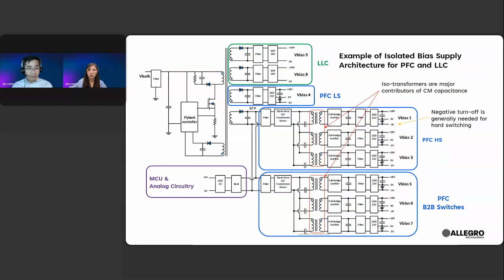An example for the PFC high side negative supply design: we get 12 volts from the flyback converter, and then use either open loop LLC or open loop push-pull to generate bias supply rails 1, 2, and 3. Each rail can have a separate transformer for common mode capacitance reduction, and the output of the open loop LLC generally needs to be regulated because it's load dependent.